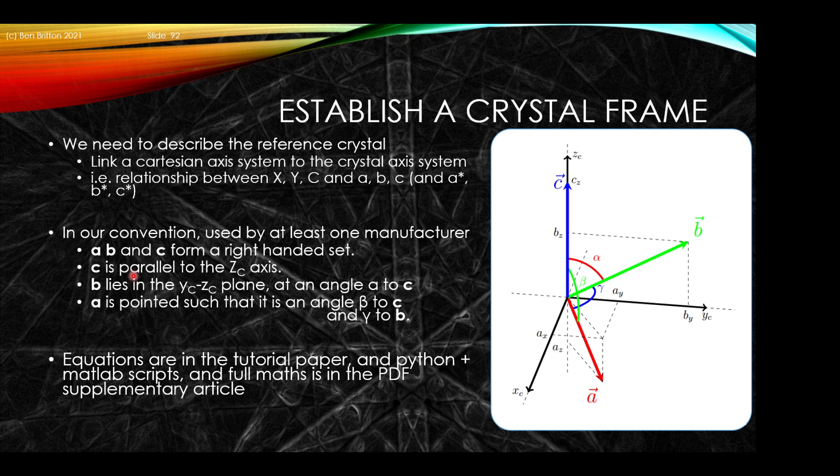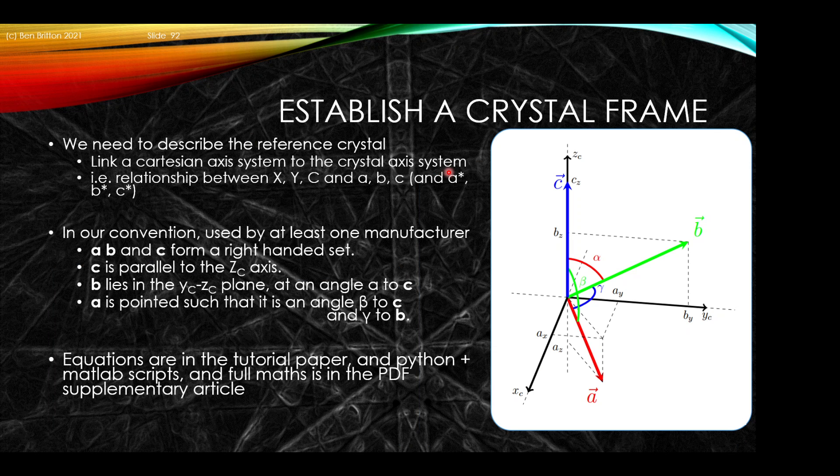Once you've done that, we need to think about how we establish the reference crystal. We want to link a Cartesian axis system to the crystal axis system, the relationship between X and Y to A, B, and C, and specifically also to the reciprocal lattice vectors A star, B star, and C star. In our convention, which is used at least by the Bruker system, we say that A, B, and C form a right handed set. We say that C is parallel to the Z_c axis. B lies in the Y_c, Z_c plane at an angle alpha to C. A is pointing at an angle beta to C and an angle gamma to B. So C is pointing along Z_c.